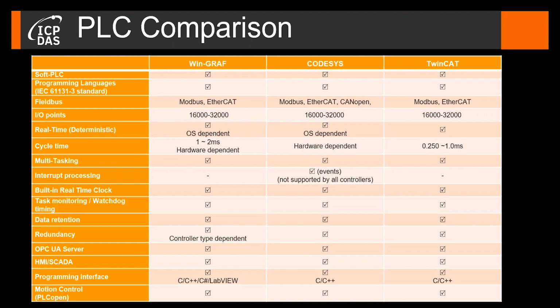Soft PLCs are mainly used for decentralized I/O control, like controlling of an EtherCAT or Profinet network, while traditional PLCs focus on centralized I/O control. So the number of I/O points supported by soft PLCs is almost unlimited, while the number of I/O points of hard PLCs is limited by hardware and local I/O expansion boards. Soft PLCs, compared to hard PLCs, also have the ability to manage and store large amounts of data because the PC memory size is considerably larger than that of a hard PLC.